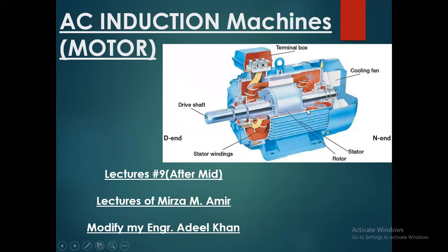All the people very well know about the AC induction motor and the components and further sections in the induction motor. You can see in this figure the terminal box by which we provide supply to the stator side of the induction motor, and at the end side, for cooling purposes, there are three cooling mechanisms in a single induction motor, either single phase or three phase. The first is its structural heat sink, you can see it available here, and the cooling fan at the end side works as an exhaust to extract the heat from the motor and exhaust it in the air, and at the end side the cooling holes are also available there.